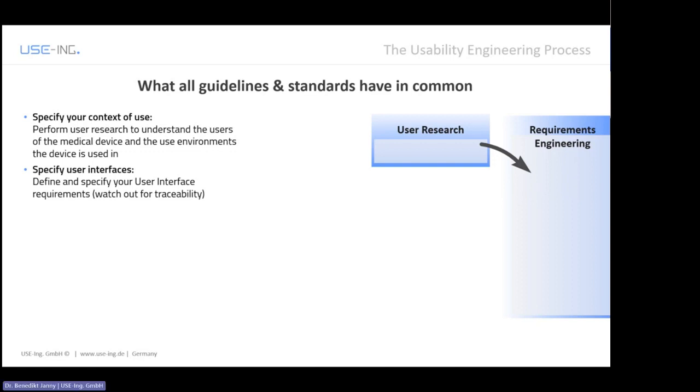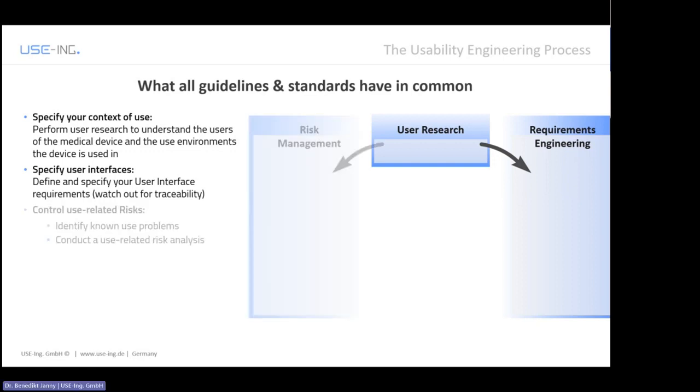Like for all aspects of medical device development, risk management is key. So of course we have that link to use-related risk. And therefore we must control use-related risk by identifying our known use problems and conducting a use-related risk analysis. All of them require us to do so.